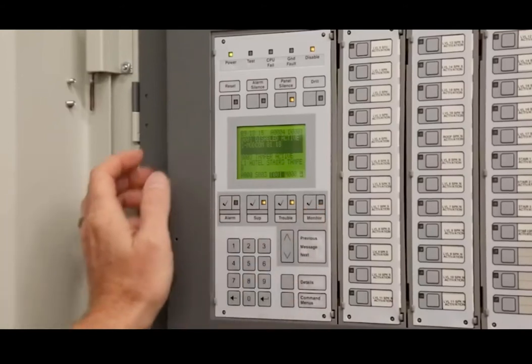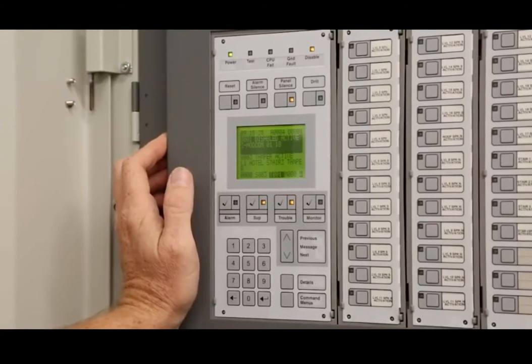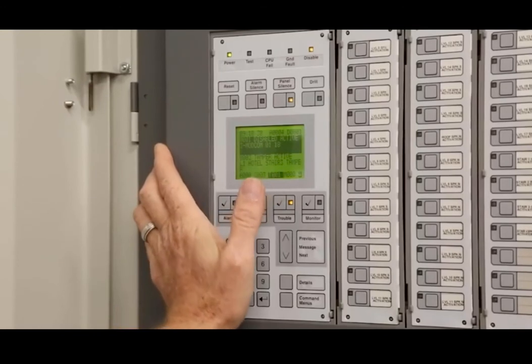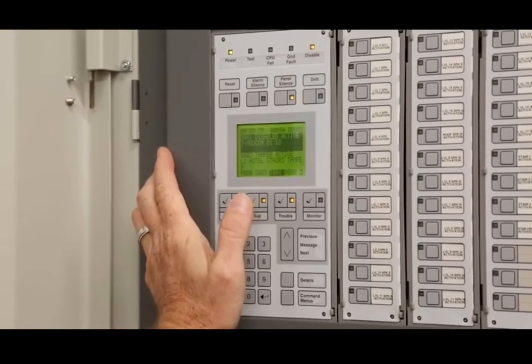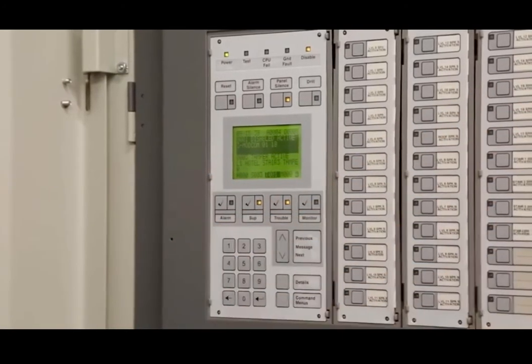Monitor points are basically any damper, the damper indication, or fans are monitored. If we are in smoke control mode and we do have a smoke detector go off on the floor, this can actually go up to 60 points because there'll be monitor points on your dampers and fans and all that. Also, monitor points would be any switches that are activated here.